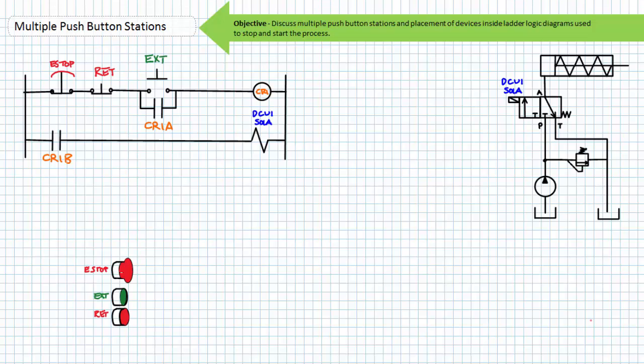When the coil of control relay one is energized, its associated contacts would change states. The normally open CR1A contact in rung three would close. The now closed CR1B contact energizes the A solenoid of DCV1. The energized solenoid A would shift directional control valve one to the straight-through position and the single acting cylinder would extend. Note that all it took to initiate extension of this cylinder is energizing the coil of CR1 by providing a path for current. If an operator were to release the momentary contact extend button, the spring return would return it to its normally open deactivated state. Note that the now closed CR1A holding contact would maintain the energized state of the CR1 coil, meaning the CR1B contact would stay closed and the A solenoid of DCV1 would remain shifted to the straight-through position and the cylinder would continue to extend.